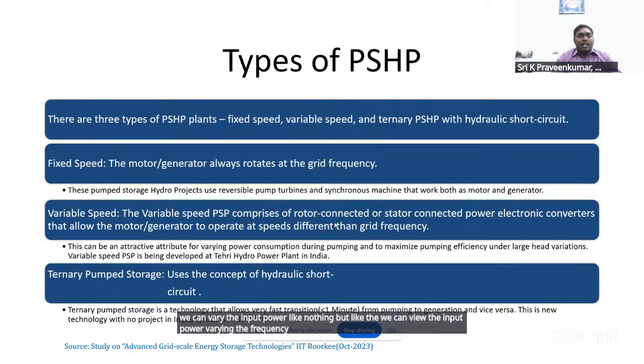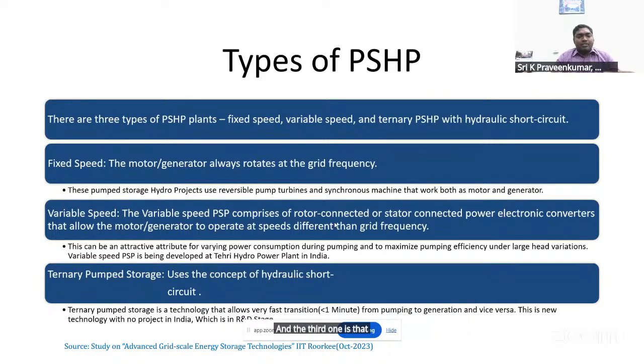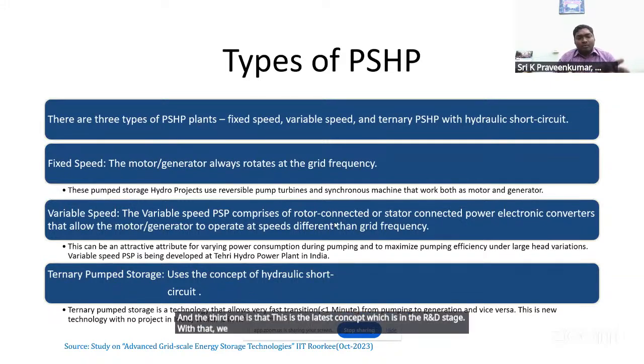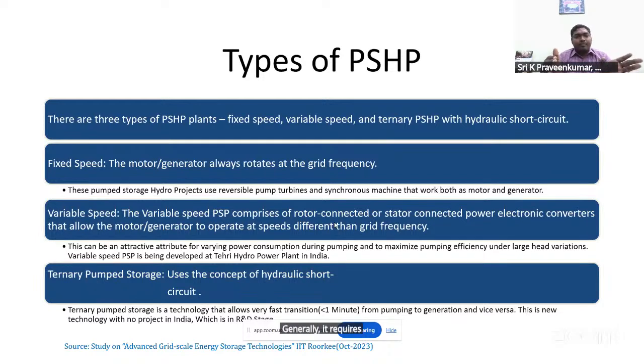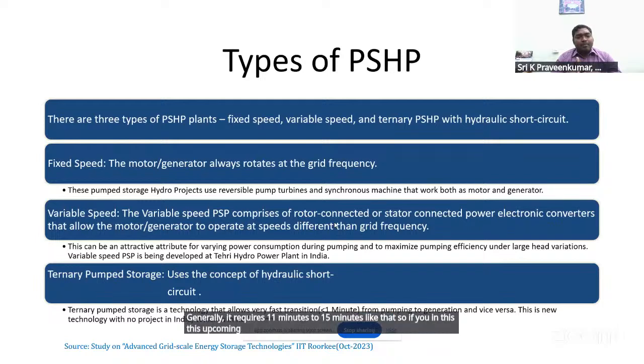The third one is ternary pumped storage, the latest concept which is still in the R&D stage. With that, we can get a much shorter response time, less than 1 minute. Normally, switching from pumping mode to generating mode requires 11 to 15 minutes, but this upcoming ternary pump storage type allows a very fast transition.